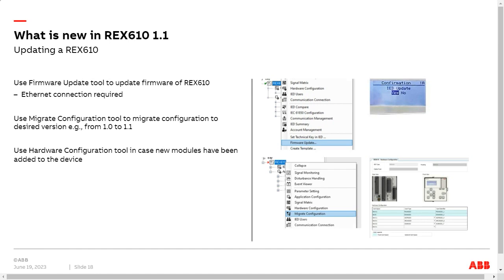And then this third bullet: use the hardware configuration tool in case modules have been added to the device. Of course, this is not needed if you don't want to add anything, but if you have added the ARC module into the device, then you need to open up this hardware configuration tool and state that in slot D1 you now have this ARC 2001 module. And after that, that's it.